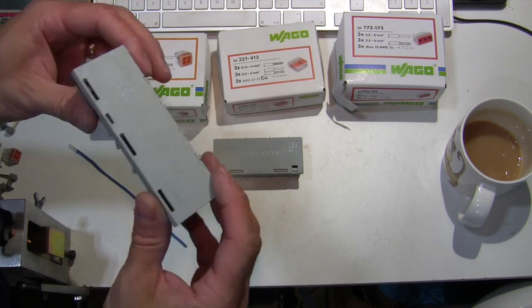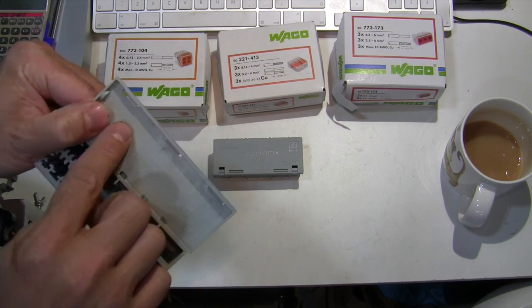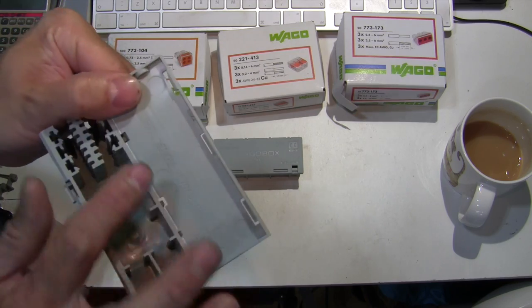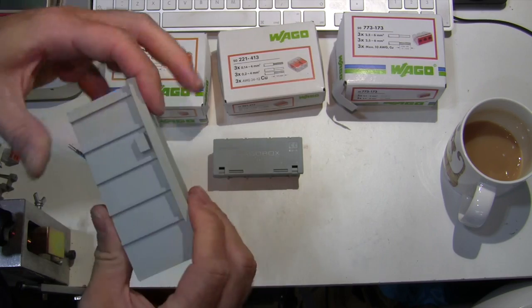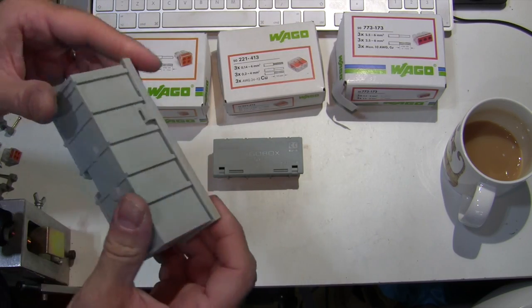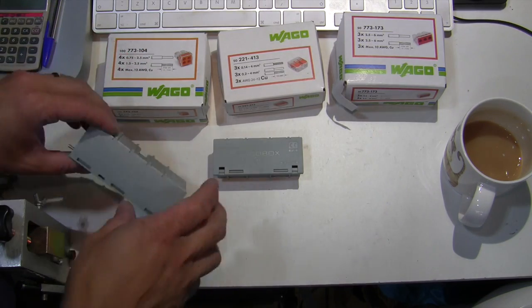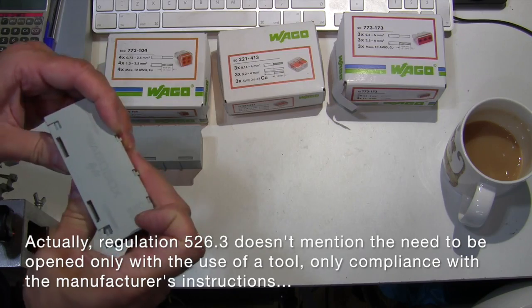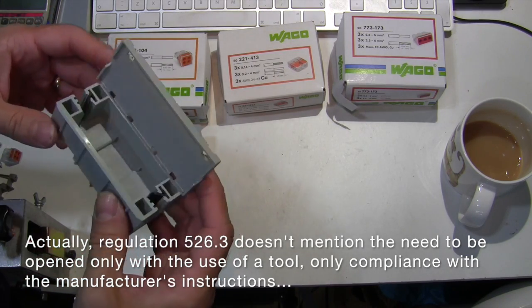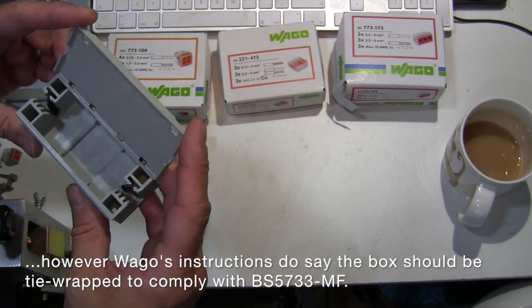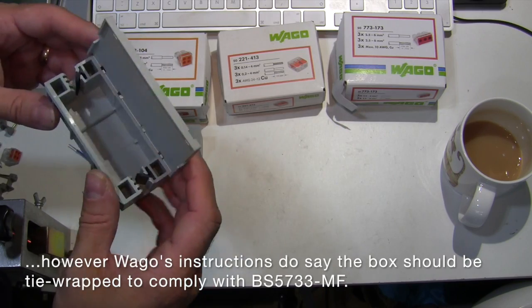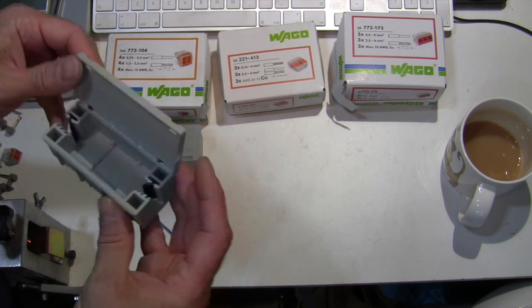Do they fall under the category of maintenance-free boxes? Yes, they do, because they are marked with an MF symbol to indicate they are maintenance-free. Very difficult for the camera to pick out, but it is there. And also it's sealable via a cable tie through the hole here, which means that it can't be reopened without the use of a tool. I don't know why you'd bother cable tying them, or why the regulations say you should. Personally, I don't. It just doesn't seem to be any point to me. If it's going to be out of the way, under a floor or above a ceiling anyway, then if you did need to get to it and you've had to break a bloody hole in the ceiling, why would you then want the additional hassle of having to chop open the box?